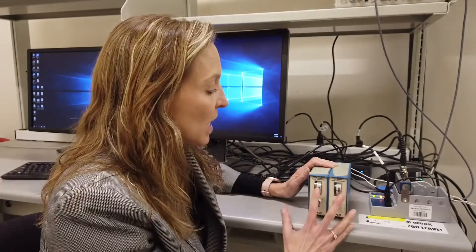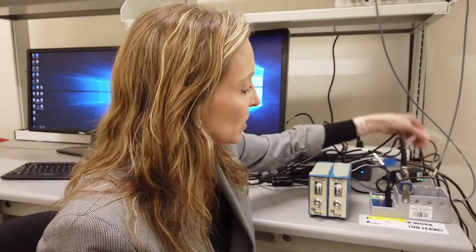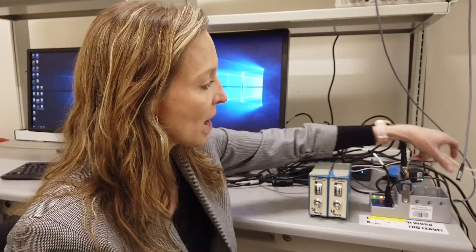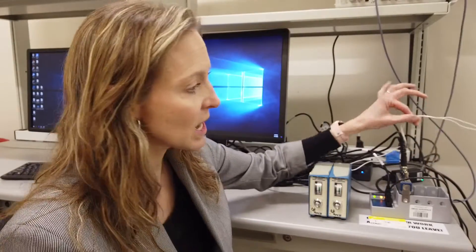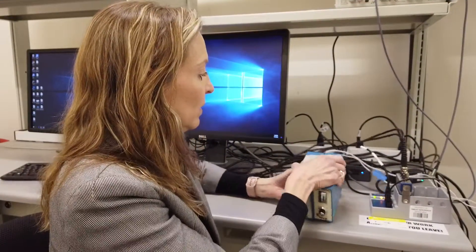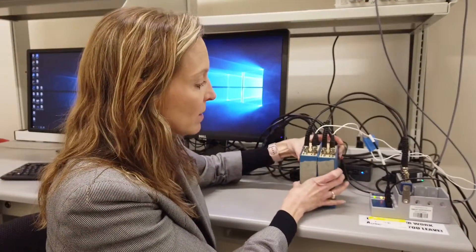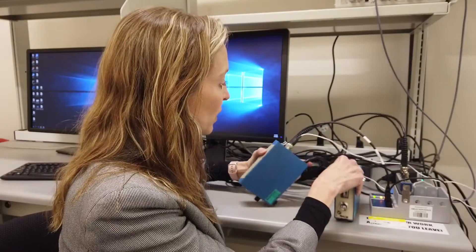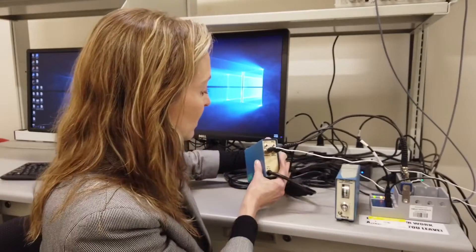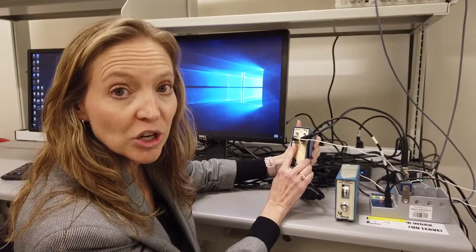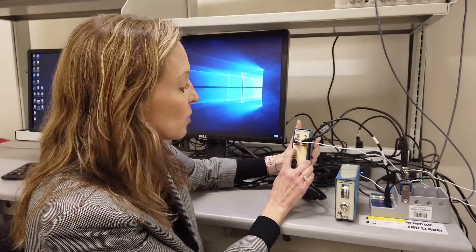The really interesting thing about these sensors is the small white wires that you see here have only two wires in them, but they are both transmitting power and current to the sensors as well as receiving data back on those same two lines.